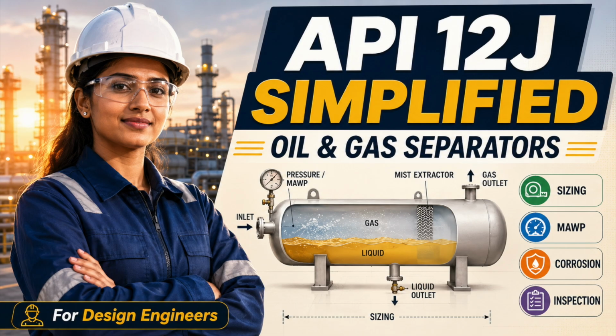Good level control is not merely tuning a controller. It is vessel volume, measurement, valve sizing, nozzle location, process dynamics, and protection working together. Pressure control matters equally because operating pressure affects gas density, gas volumetric flow, flashing, and separator capacity. A hunting pressure controller can create unstable separation even when the vessel is otherwise adequate. Pressure control valve sizing, downstream pressure variation, compressor interaction, available pressure drop, noise, vibration, and fail position all influence performance.